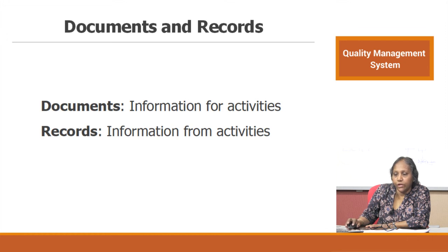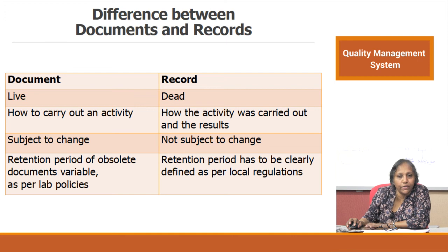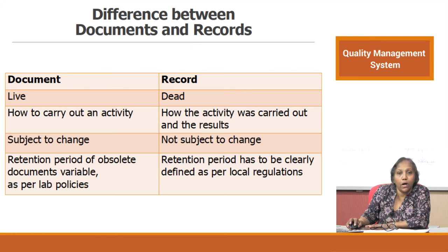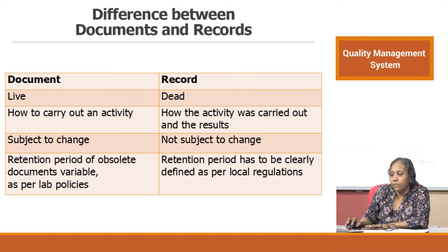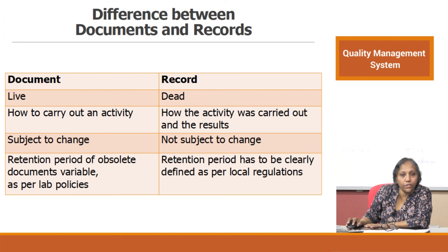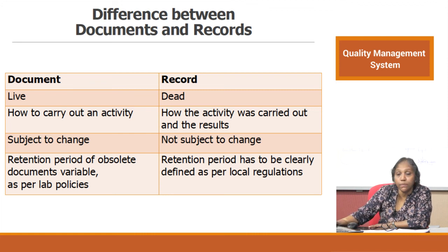Documents provide information for activities; records provide information from activities. Documents are live entities; records are non-live. Documents tell you how to carry out an activity, whereas records show how the activity was carried out and the results. Documents are subject to change; records are not. The retention period of obsolete documents is variable as per lab policies, whereas the retention period for records must be clearly defined as per local regulations — every regulatory body has mandatory requirements on record retention.